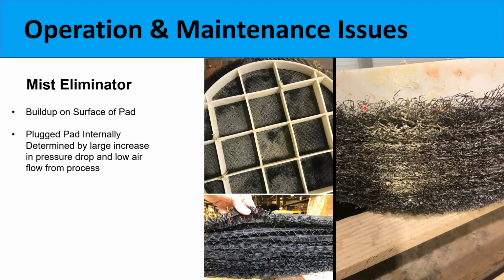This style of pad is more of a random weave mesh, and we've also used other style pads, which in the lower left corner of the picture has a structured three-dimensional grid that comes in layers that are more easily pulled apart and cleaned. So depending on the pad type you use and the configuration, you can oftentimes pull that pad apart, clean it with a hot water pressure washer in a contained area or a warm water pressure washer, and reuse that pad in the future.